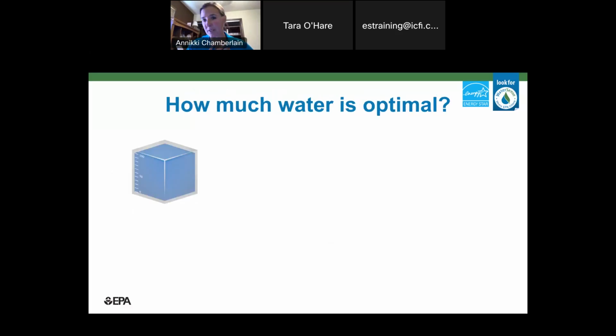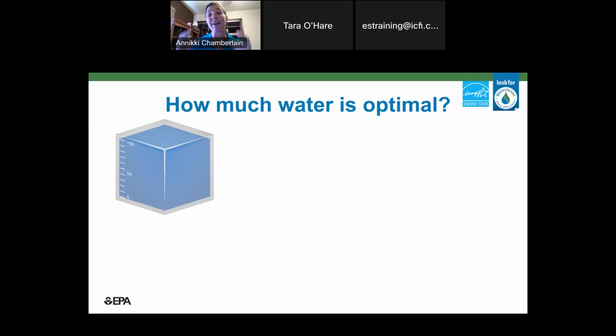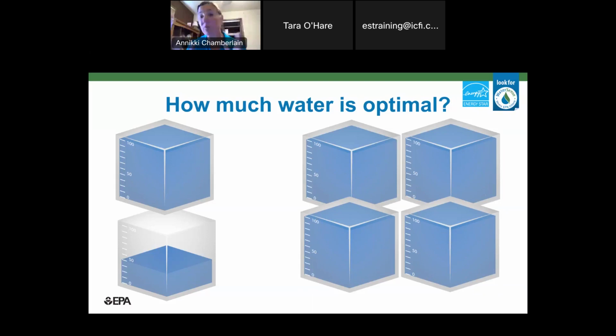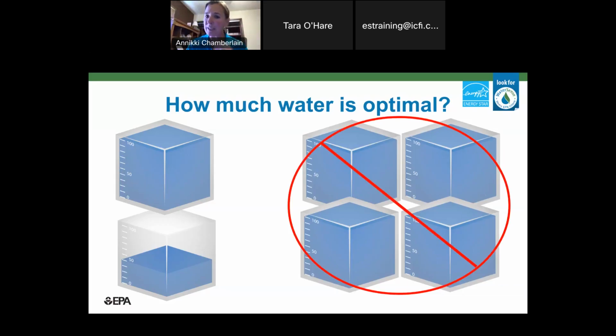So how do we know how much water is optimal for our tower? Well, there is an optimal value. I like to think of it as a cube, or a volume of water, that your tower needs to operate correctly and not waste. Now, this cube may be bigger or smaller depending on the year. Hotter years, you might need a larger volume of water. Cooler years, less. This is the same as irrigation. And we might even need 1.5 cubes just to make us feel comfortable, so we're not right on the edge of that scale. But oftentimes what we see is people using 3 or 4 cubes, 3 or 4 times the water they need, when we really don't need to do that. We just have an optimal amount, because scale comes typically from failure events, not from lack of water.